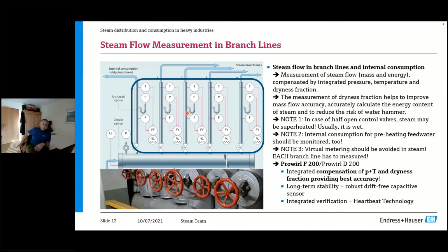On the other hand, superheated steam may occur as well. Why? Because you have these isolating valves sitting here, and in case you don't open them fully, you throttle, and this throttling effect is going to result in superheated steam. So you have relatively dry steam sitting here on that side, and if you throttle that very far down, you reduce the pressure, and then you're going to get superheated steam, and only the Prowirl F200 can tell you how many degrees of superheat you have. So this is very helpful there. You always know where you're at on the Mollier chart.